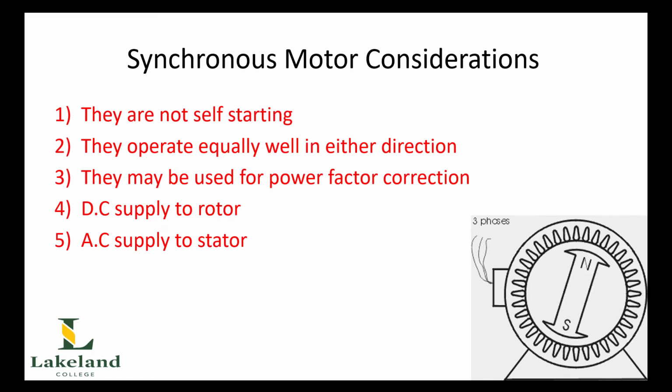Well, like you saw on the video, when this thing first starts up, the rotating magnetic field in the stator is whipping around at synchronous speed. But the rotor upon startup is stationary. Well, there's a massive relative difference in motion between the two. So there isn't time, due to the inertia of the rotor, which is the rotor's tendency to resist a force to actually move, there isn't time for it to magnetically lock and move around. Because by the time it locks on, the opposite poles move past, and it's now repelling on the next pole. So this is why these things can't start up on their own. They need some other method, and we'll talk about that on the next slide.